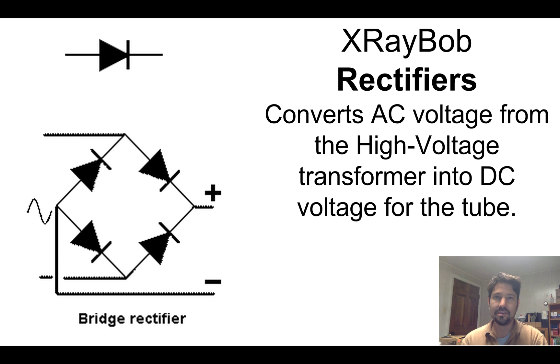All right, so they convert AC voltage from the high voltage transformer. So we stepped up the voltage to high voltage, and now we're going to convert it into this pulsating DC that we're going to use to feed our x-ray tube.